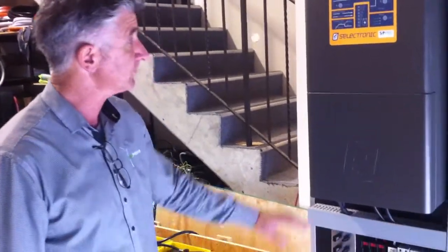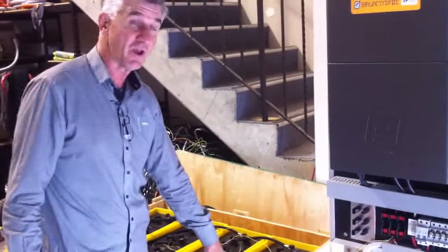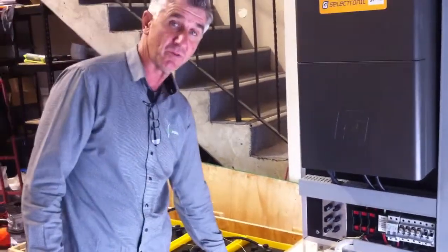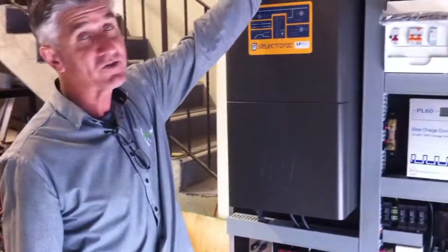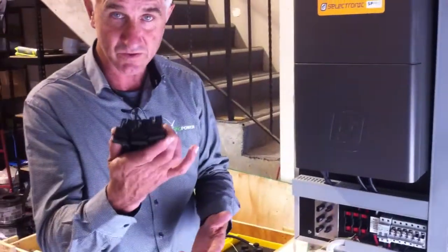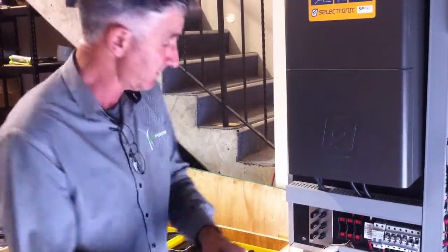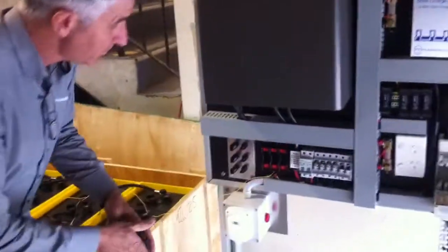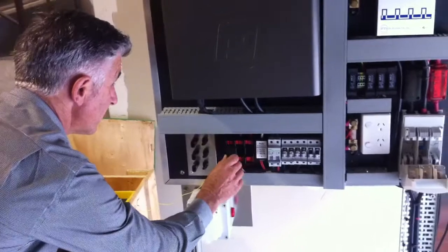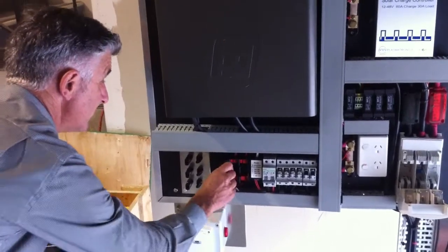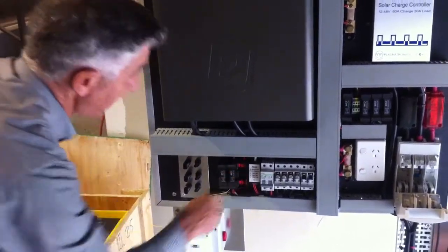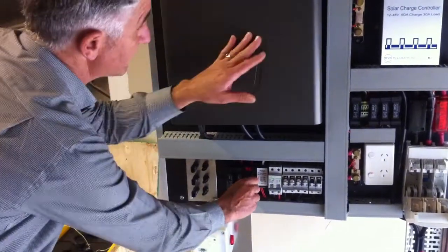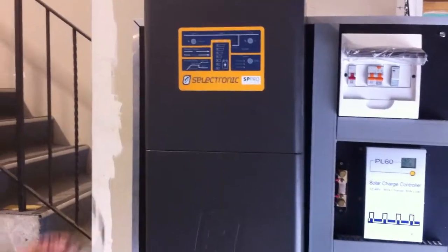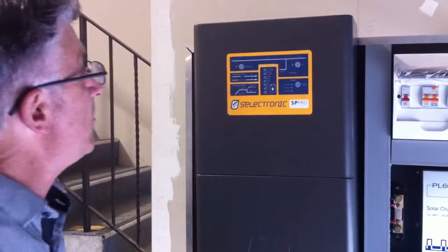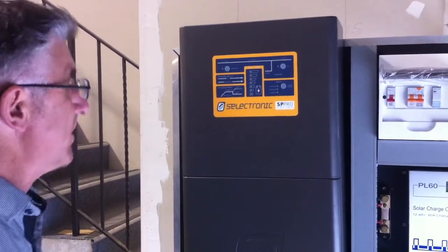So you've got your battery cables hooked up and your midpoint sensing cables hooked up. The first thing you do is put in the fuses - there's three of them - into your midpoint sense holders. Just put that in there, and you'll see the SP Pro, the inverter charger, will react. You'll see a few lights start to come on, and the alarm may also come on - just give it a second.